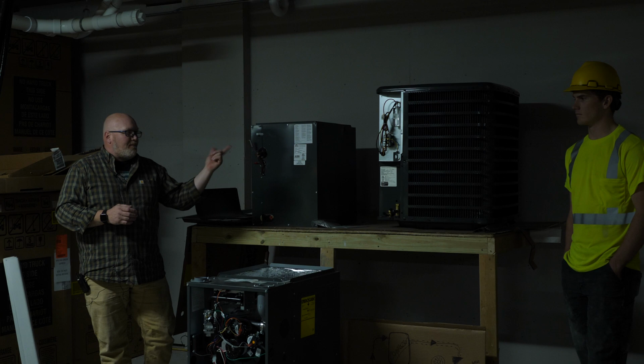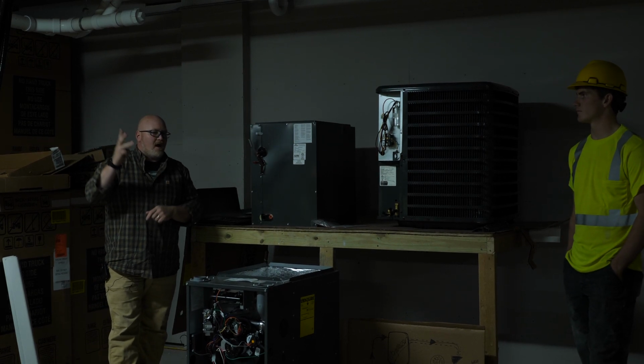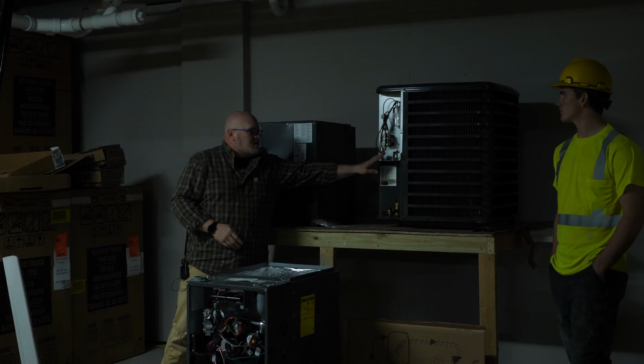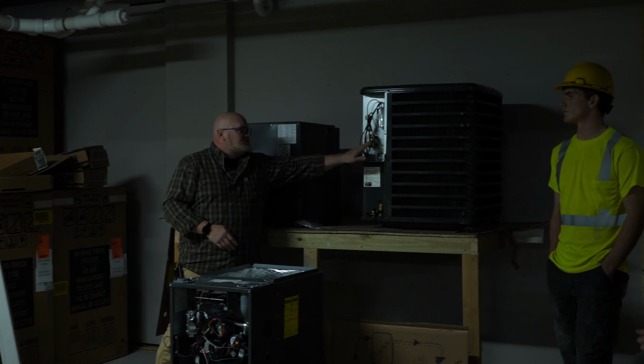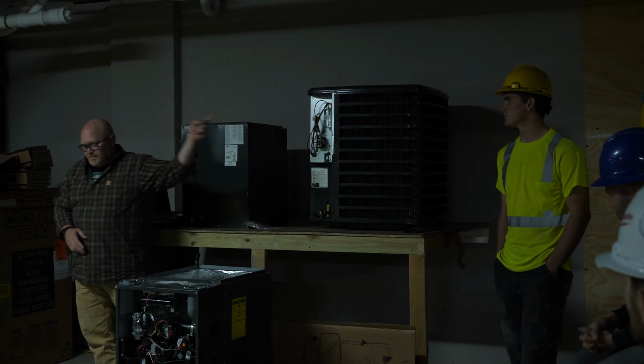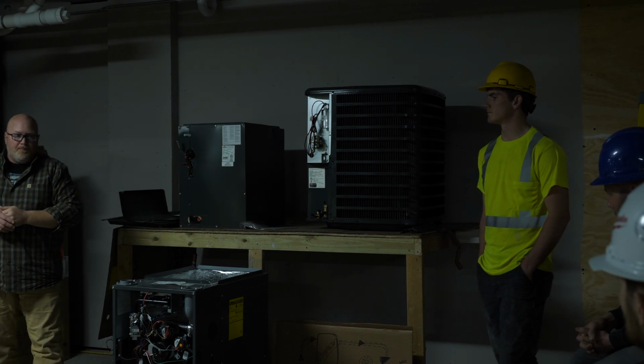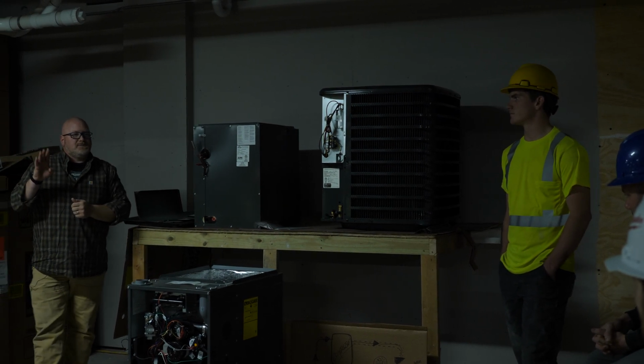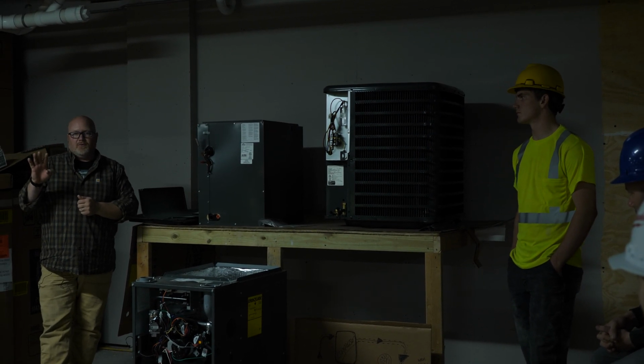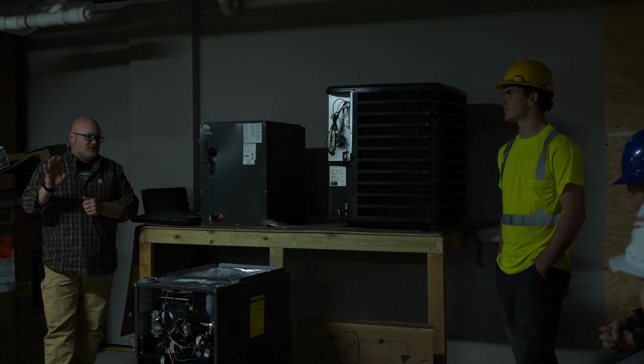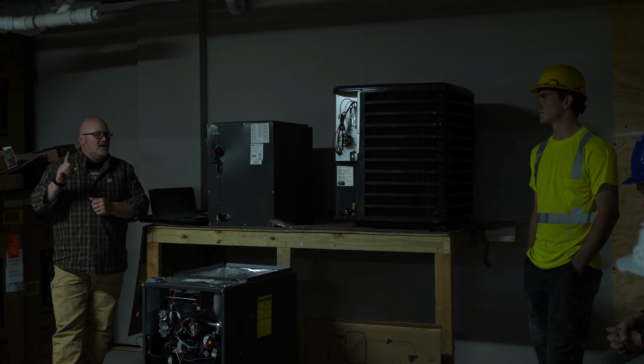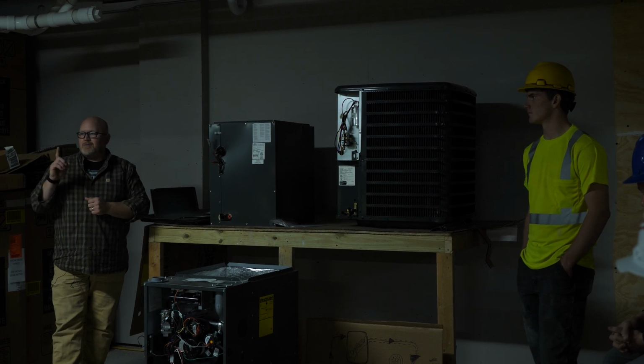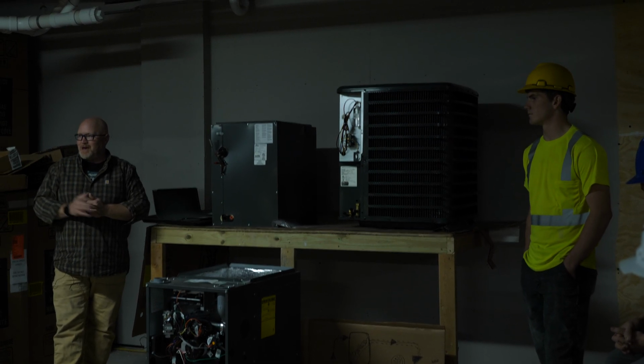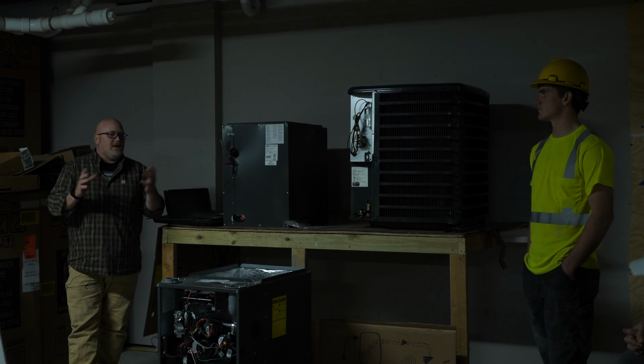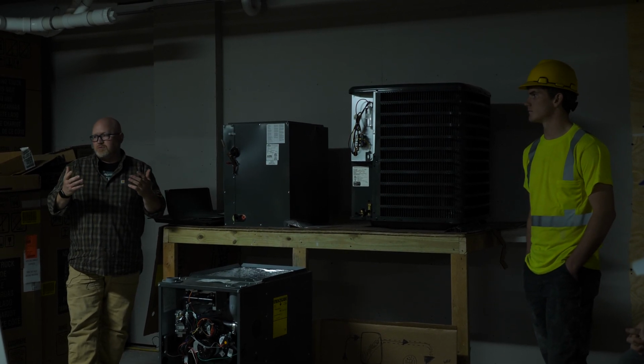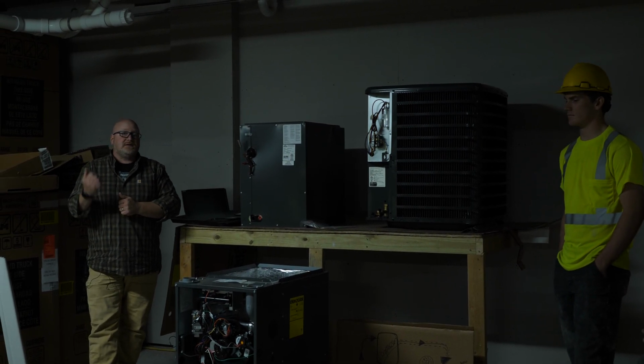So back to our parts. We've talked about 3 parts there: the parts on our compressor condenser, our contactor, our capacitor, and our condenser fan. The 4th one, and I would say this is probably the biggest one to start with. Number 4, number 5 are going to be super easy here. Number 4: are the batteries in your thermostat new or working? Okay? You'd be surprised how many people, it turns out, we just need to replace batteries in the thermostat. So that's an easy one.